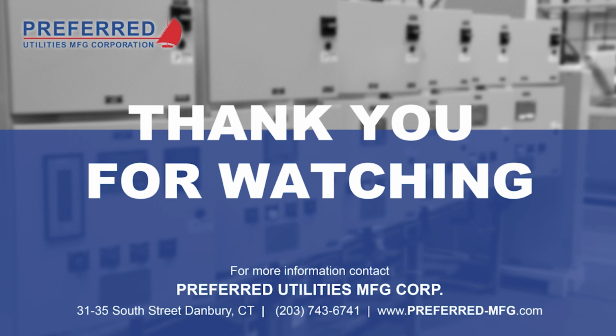Could you talk more about saturation? Because this is something I just learned about relatively recently. I was starting up an oil burner, had a beautiful flame, started it off, started working my way up to higher and higher firing rates with a good flame signal and a good looking flame. Everything looked fine, and then at about 30 or 40% firing rate, I was dropping out on flame failure.